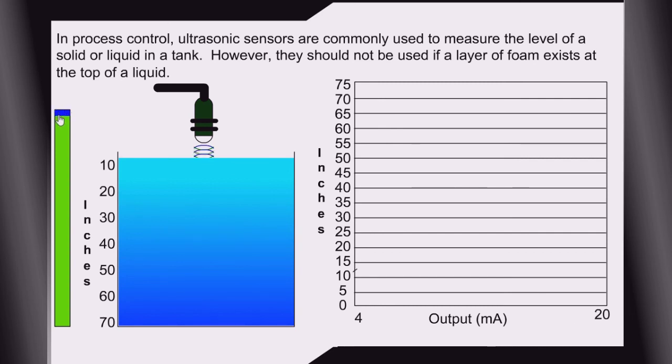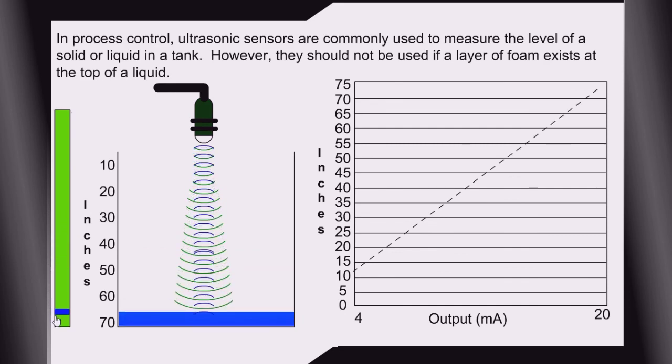However, they should not be used if a layer of foam exists at the top of a liquid. Inaccurate readings will also be made if a mist is present in the vapor space above the liquid because sound travels through a mist at a different speed than it travels through dry air.